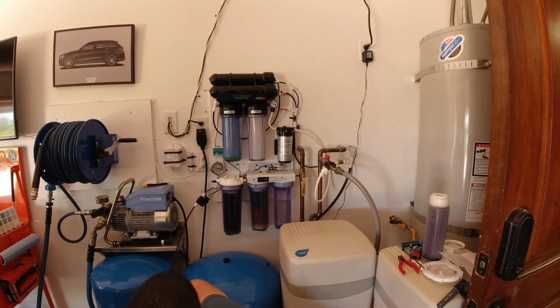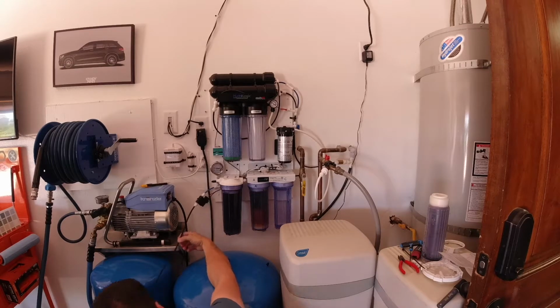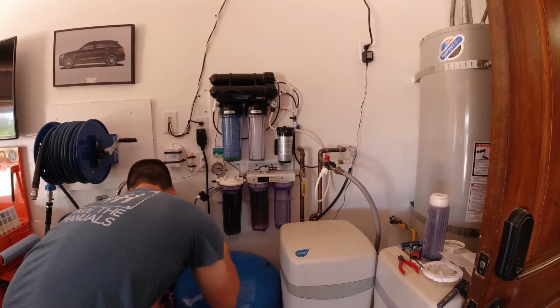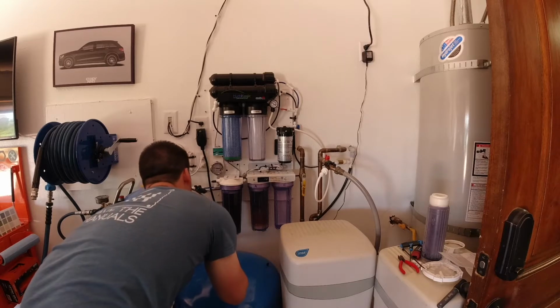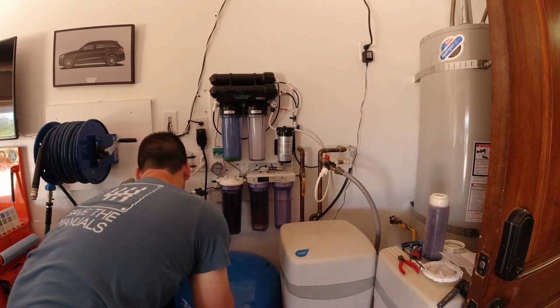If I let water out of here and drop the pressure, we can see when it kicks on. So it kicks on around 25, and it runs and runs and runs, and it shuts off at 50. That's where I've got it set right now. It's a 40 psi switch. I did adjust it a little bit, obviously, because 50 isn't 40. But I'm pretty good where I'm at.